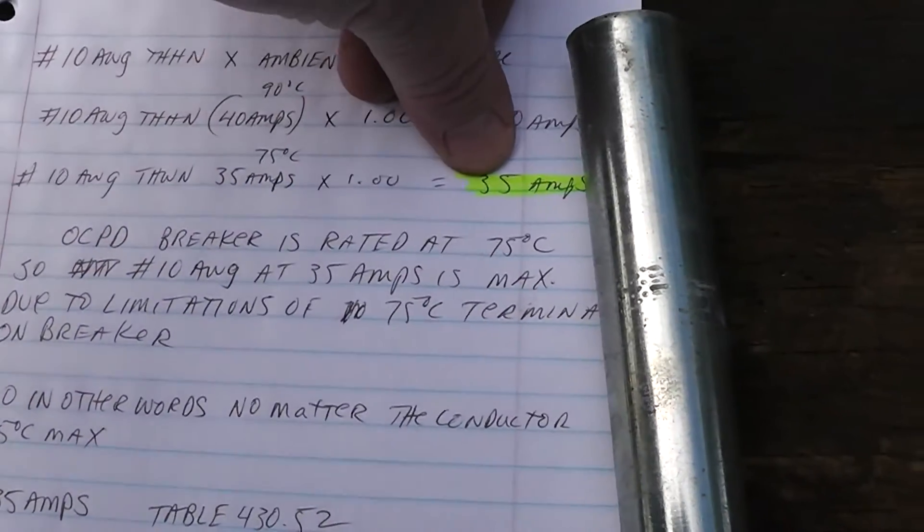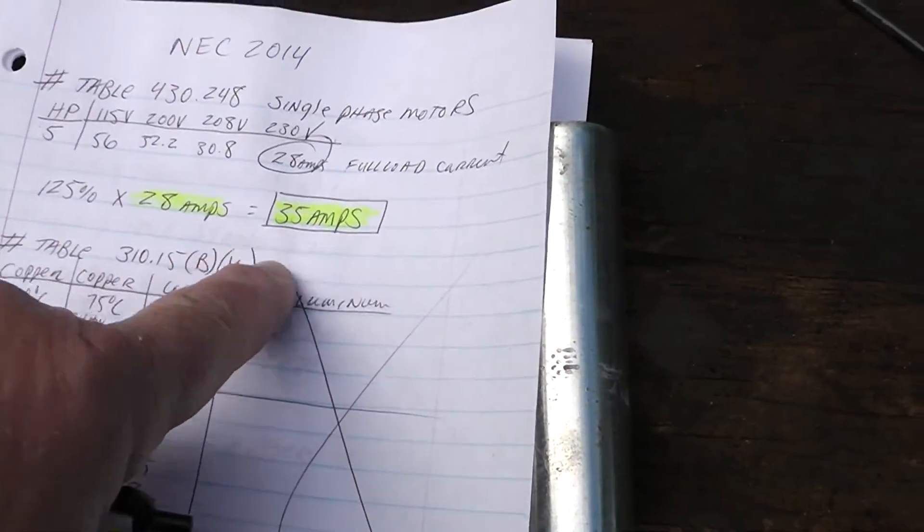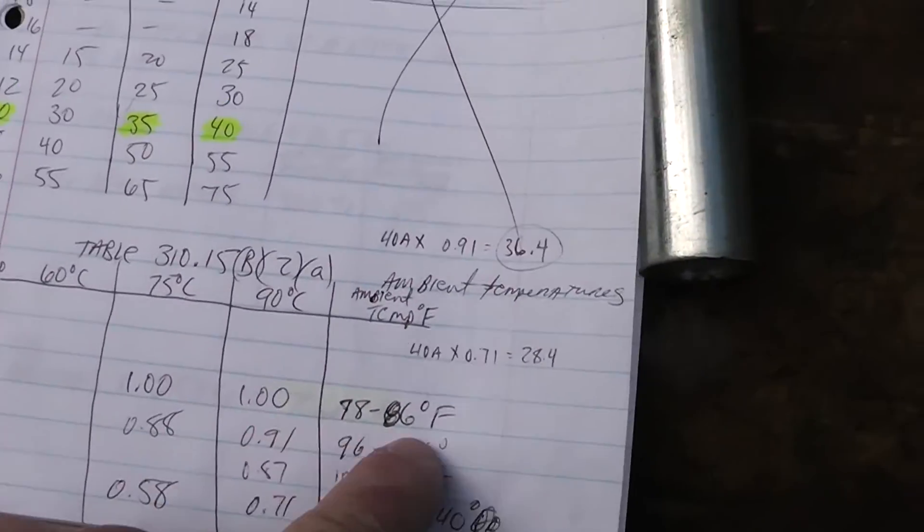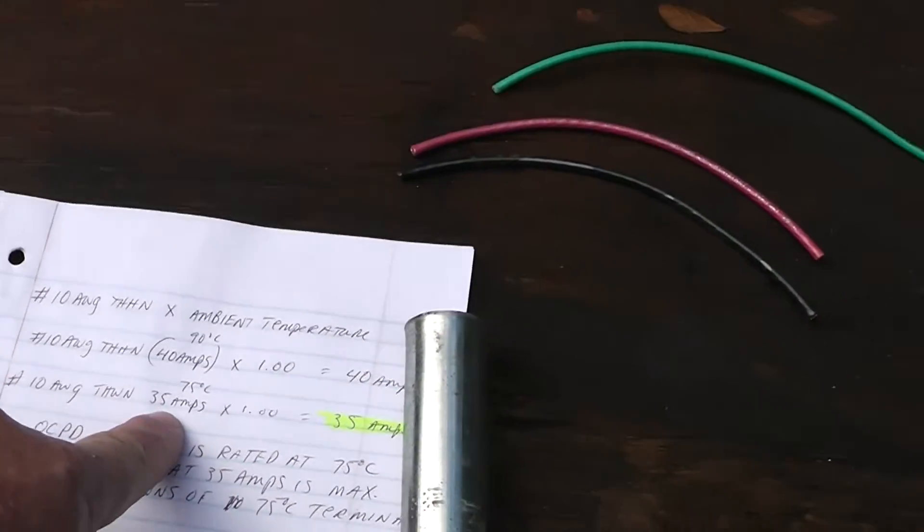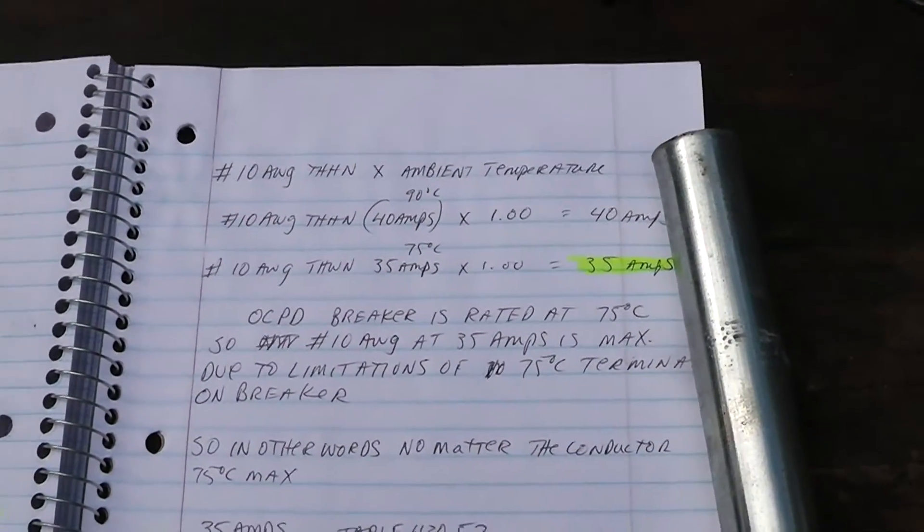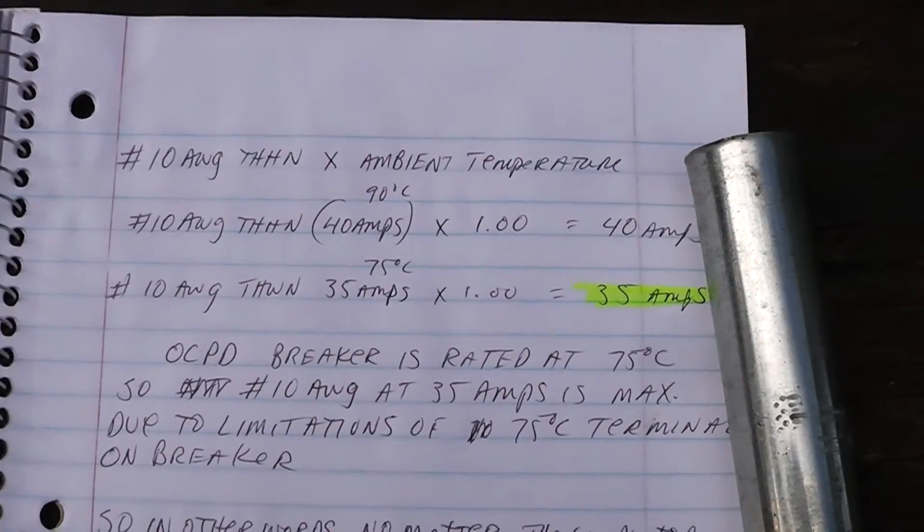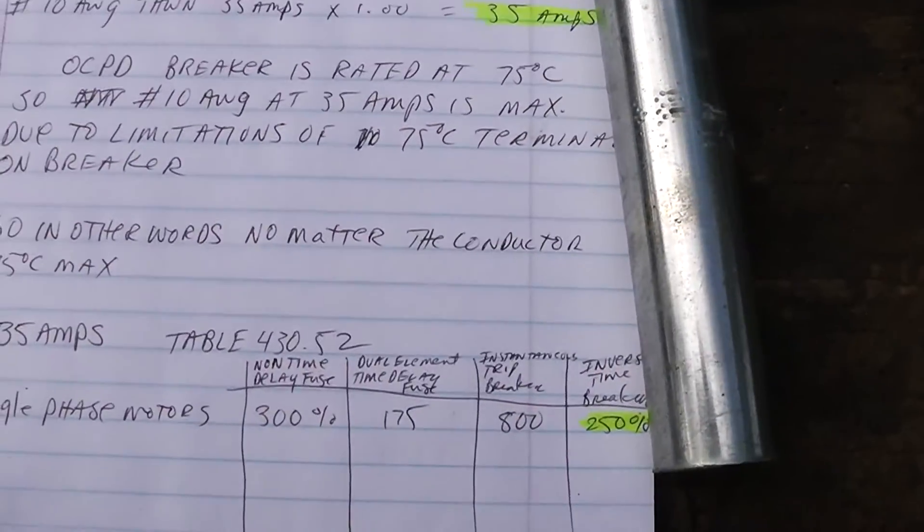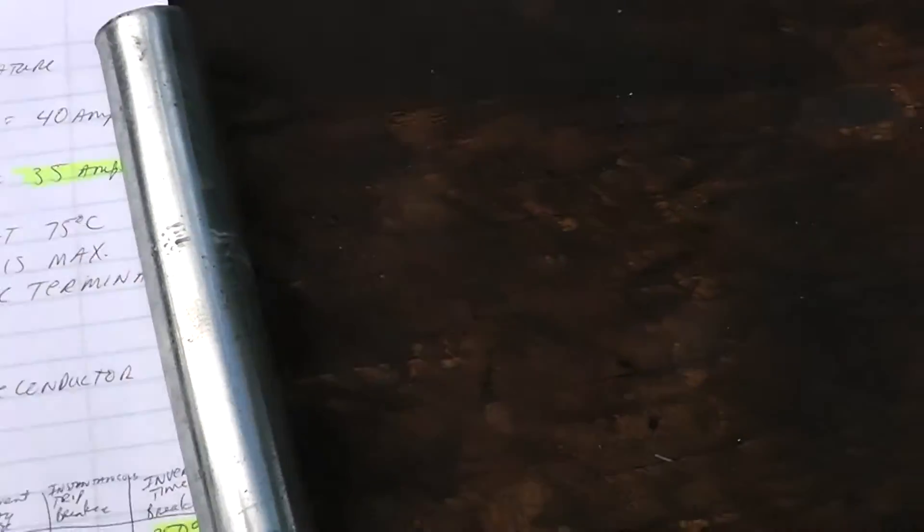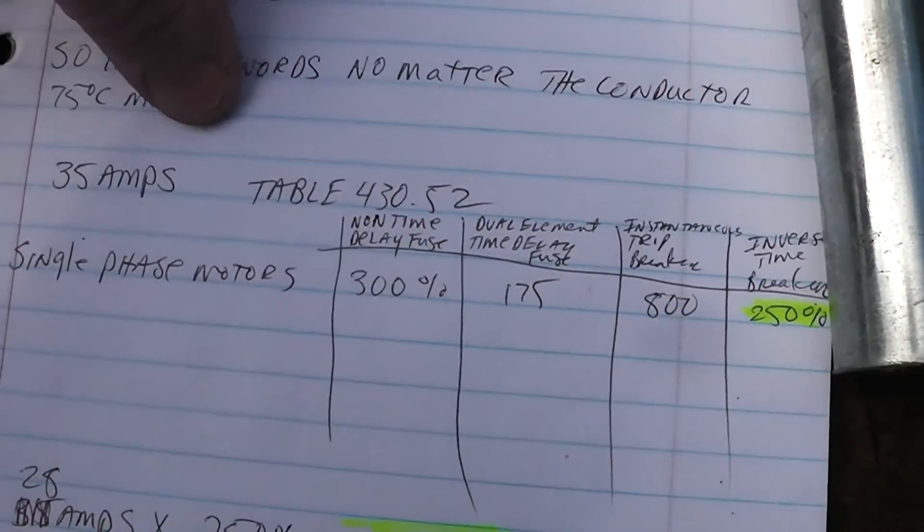If your full load amps was like 40 and you had no correction factors and you put it on that breaker, that breaker drops it down to 35 because the terminals are only rated at 75 degrees. It's like a link in a chain - you have to go by the weakest link in the chain, and when you run an electrical circuit, the weakest link in the chain are the terminals at the breaker.